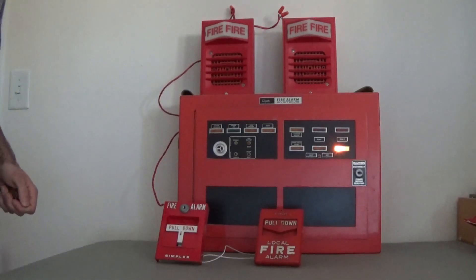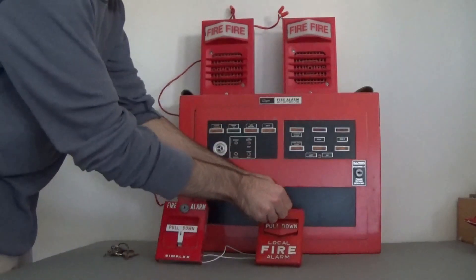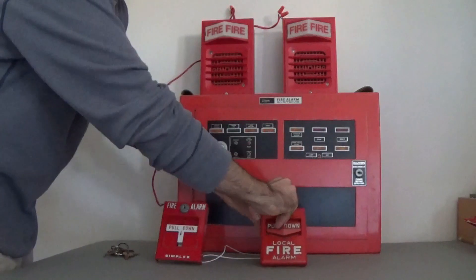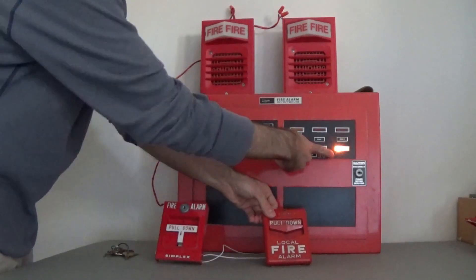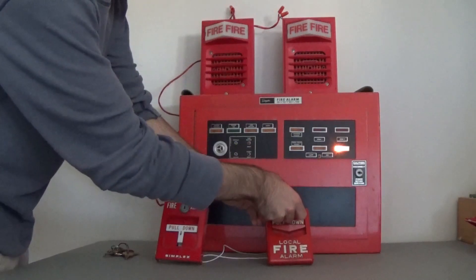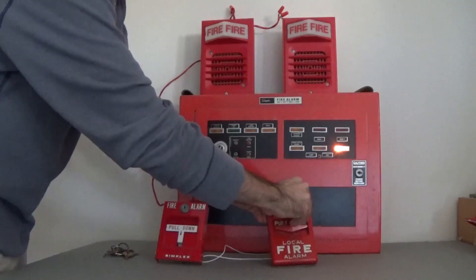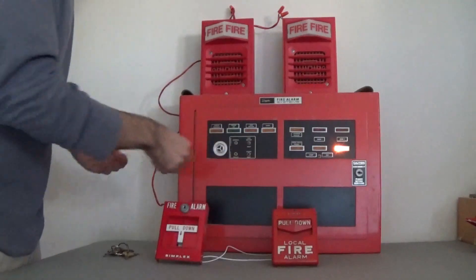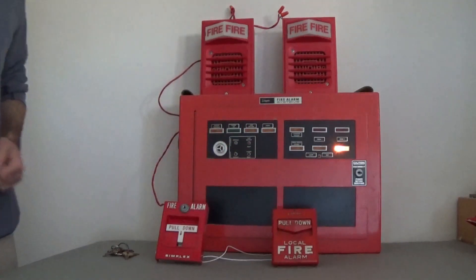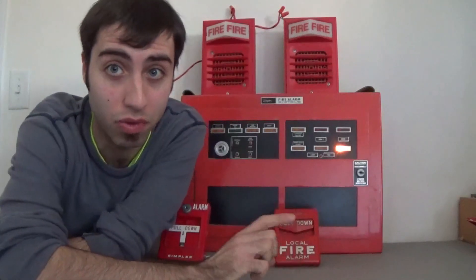Now we're going to be pulling the chevron — let me get my hex key. It looks like it latches into trouble — that's weird. Oh, I see what's happening: the trouble light turns off when the panel registers an alarm condition. So now that's reset, we're going to reset the panel and the silence switch. That's about it for today — thank you for watching everyone, don't forget to like, comment, and subscribe.